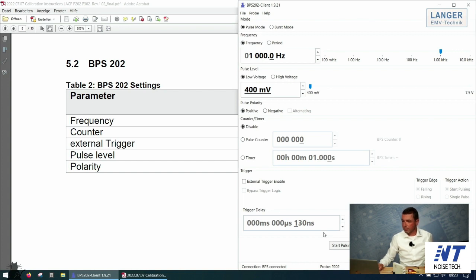Now I will explain the settings of the software. In the mode, you can change between pulse mode and burst mode. For our calibration, we need pulse mode, and the frequency of the pulses for our test is 1 kilohertz. The minimum frequency you can set is below 1 hertz, and you can go up to 10 kilohertz. That's the maximum repetition rate of the pulses.